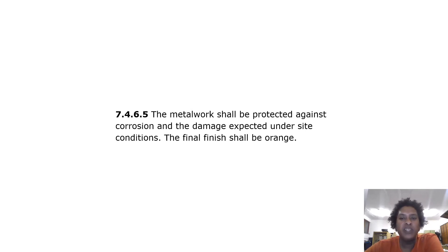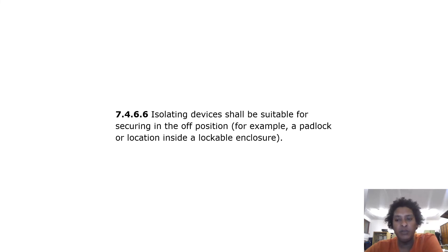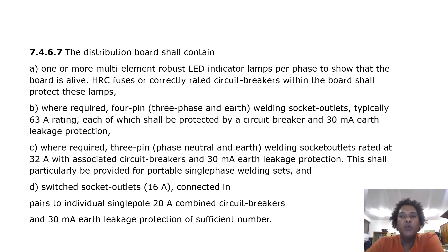The metalwork shall be protected against corrosion and the damage expected under site conditions. The final finish shall be orange. Isolating devices shall be suitable for securing in the off position, for example by a padlock or location inside a lockable enclosure. The distribution board shall contain one or more multi-element robust LED indicator lamps per phase to show that the board is alive. HRC fuses or correctly rated circuit breakers within the board shall protect these lamps.